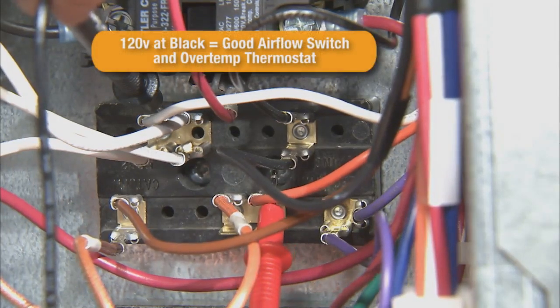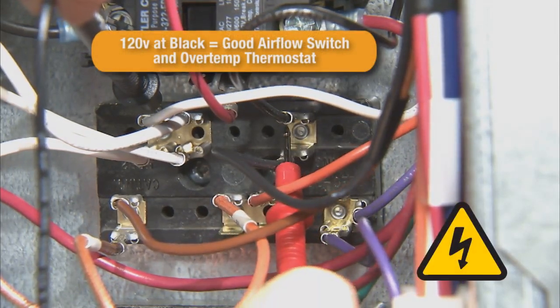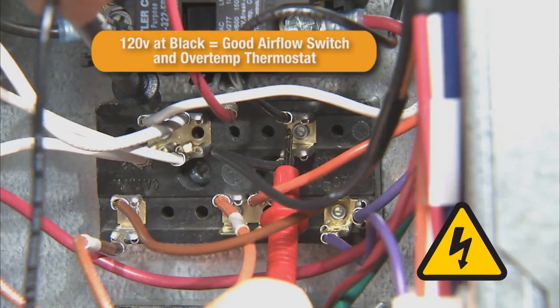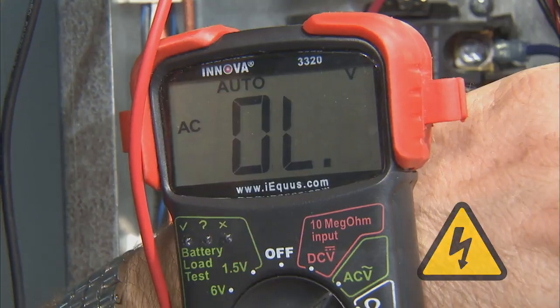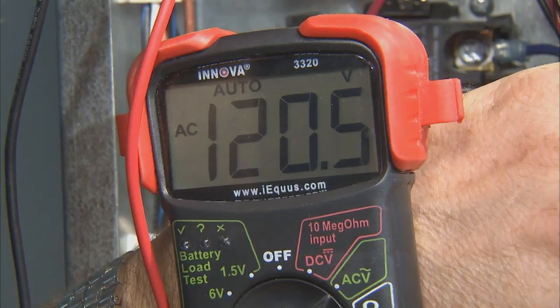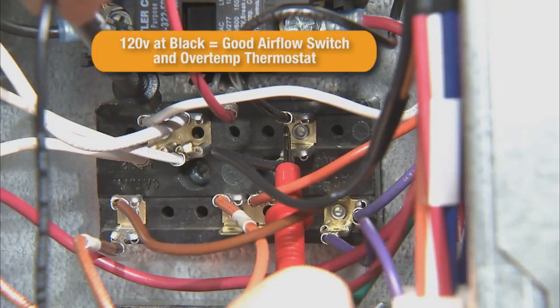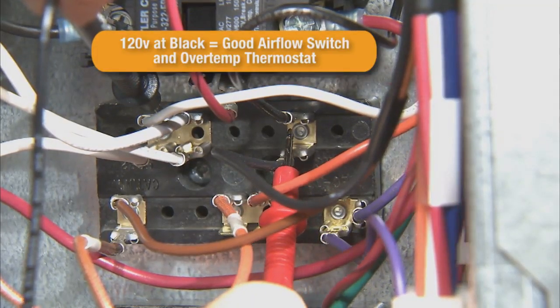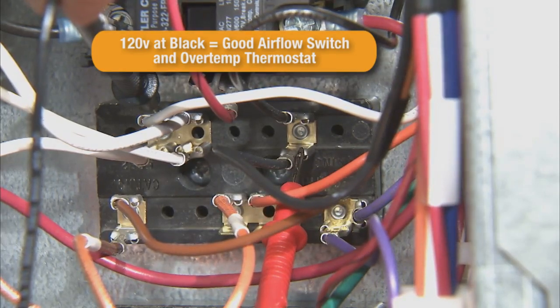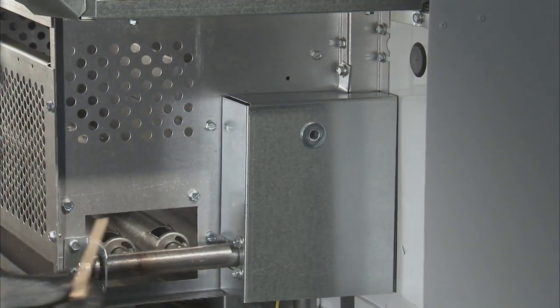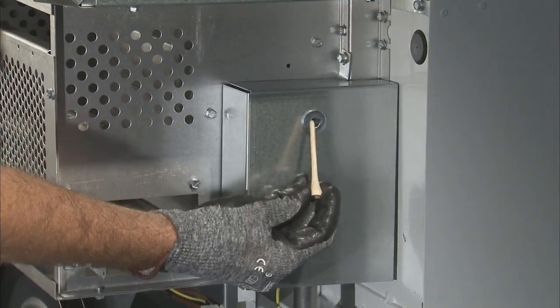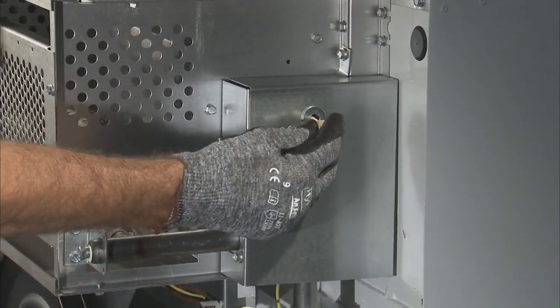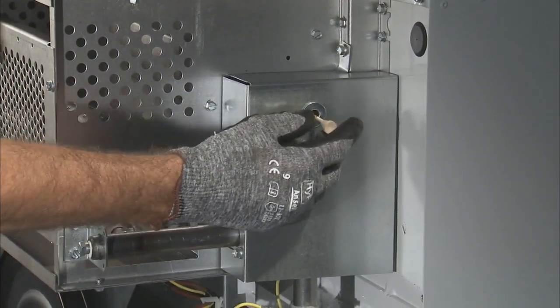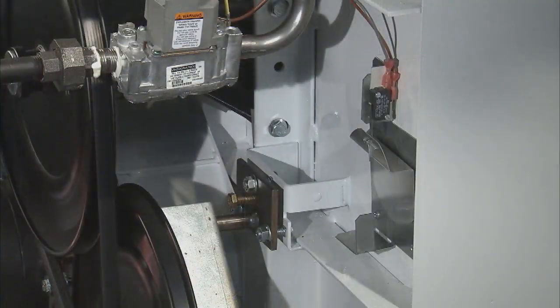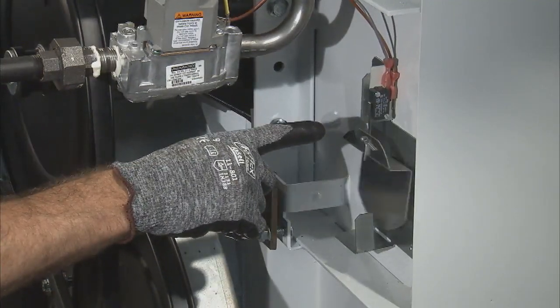The fourth test is at the black wire connection. 120 volts AC at these wires will indicate the proper functioning of the airflow switch and the overtemp thermostat. If voltage fluctuates or is not present, check the overtemperature thermostat for reset. This is done by inserting a non-conductive pencil or golf tee into the hole on the side of the thermostat. If there is still no voltage on the black wires, check that the airflow switch is functional.